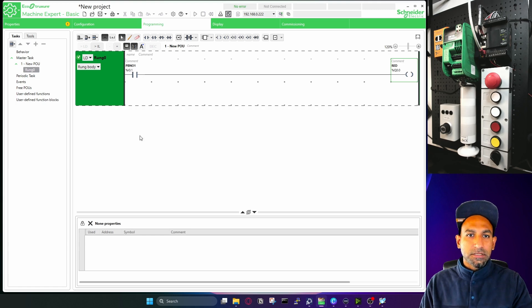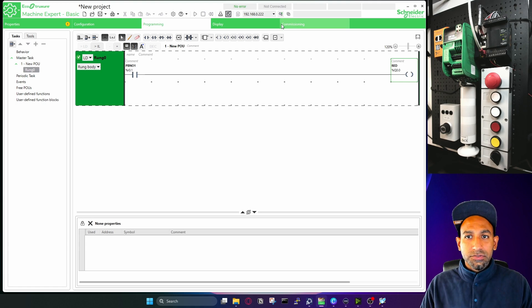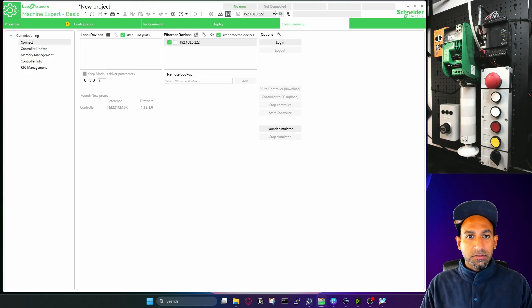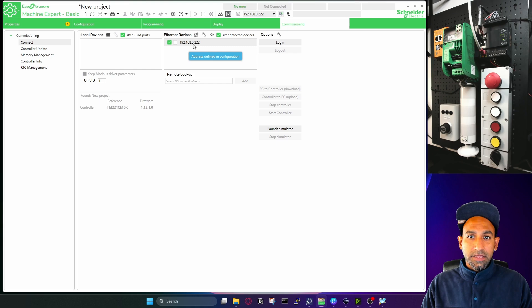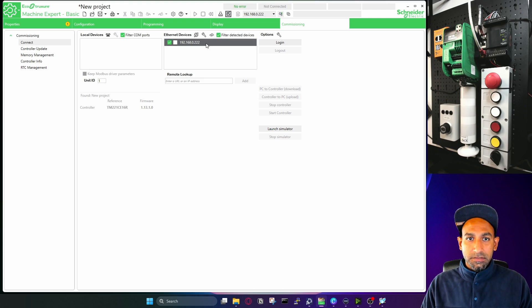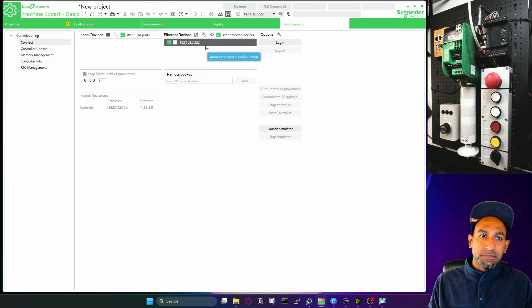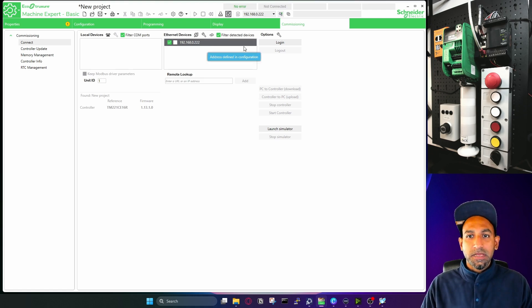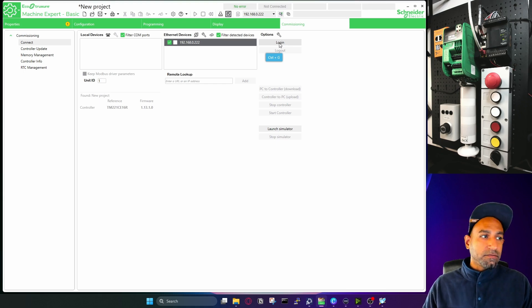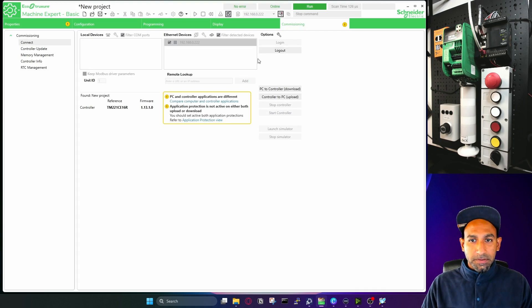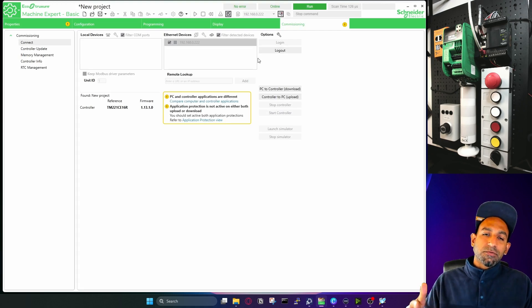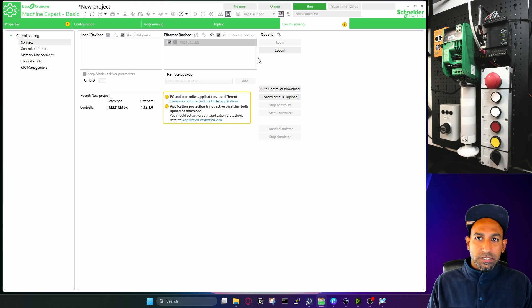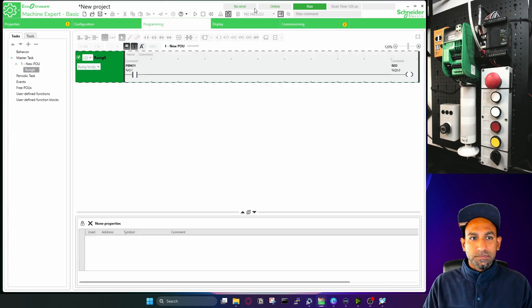Now once the logic is done, you will see it's a green tick. There are no errors there. I can go to commission. Now in the commission, you can see already I have my IP address of the PLC. If you don't see that here, what you can do is you can type the IP address here and click on add, and then you will see your IP address of the PLC. And once the software detects the PLC, it will automatically enable the login button. So because I already have a PLC on my table, I can click on login. And this will log into my PLC. And once you logged in doesn't mean the program is downloaded, you just logged into a PLC, you're just in the online mode.